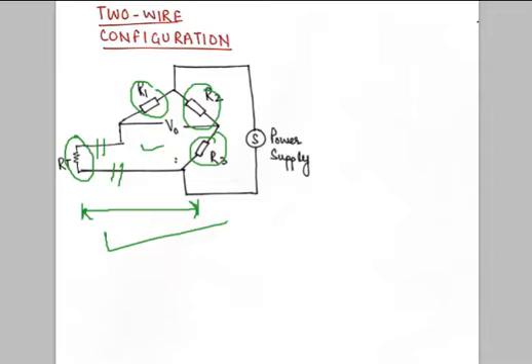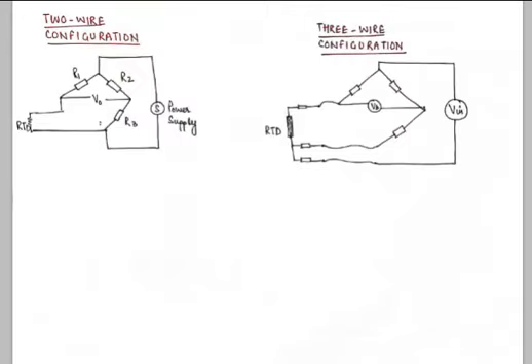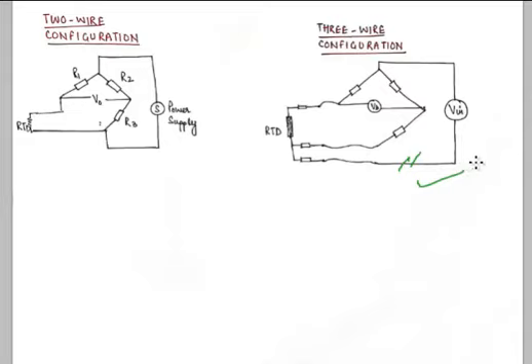When accuracy is a major concern and we cannot neglect the resistance contributed by the connecting leads, we use a three-wire configuration. A third lead — also called the compensating lead — is attached to nullify the effect of the connecting leads' resistance. All other construction parameters remain the same.